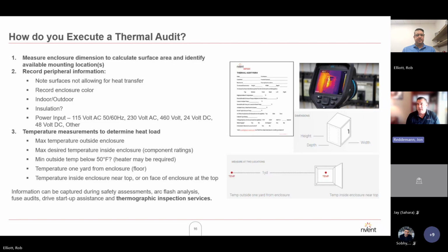It's good to know if we are just a standard Type 12 or 3R system, or if we're a Type 4 or 4X system, because we want to make sure that we match the solution to the rating of that system. And then, again, we've discussed voltage supply. If we are in an outdoor environment and we need to maintain a minimum temperature, we want to notate that, because we can calculate if heating is required, how much heat we would potentially need for that, right?